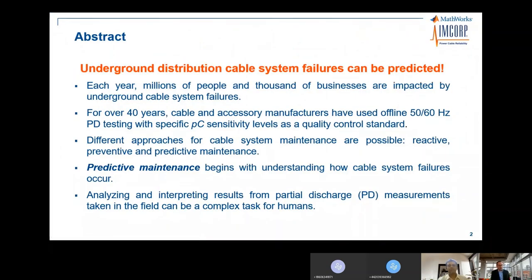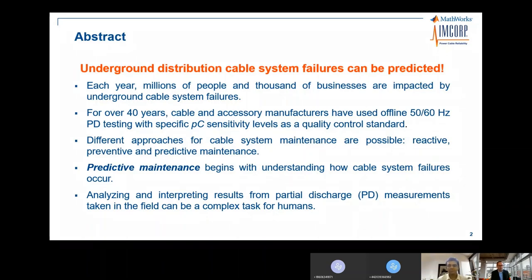Underground distribution cable system failures can be predicted. Each year, millions of people and thousands of businesses are impacted by underground cable system failures. For over 40 years, cable and accessory manufacturers have used offline 50/60 Hz PD testing with specific sensitivity levels.